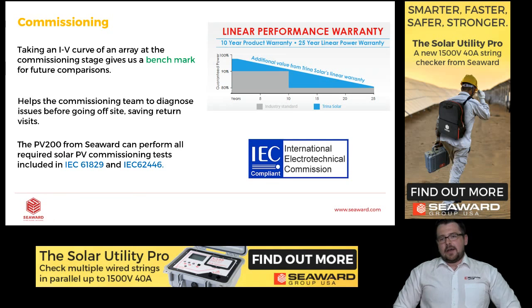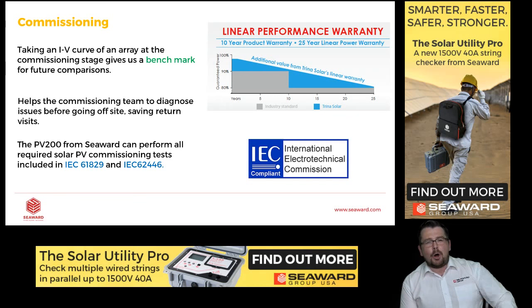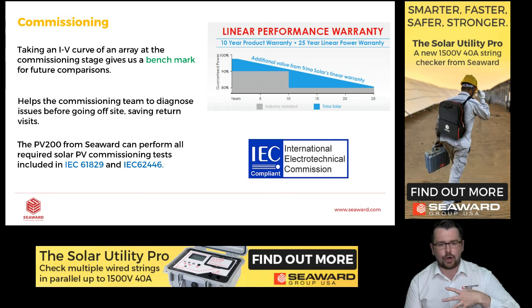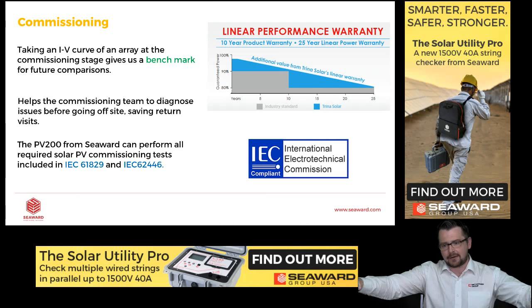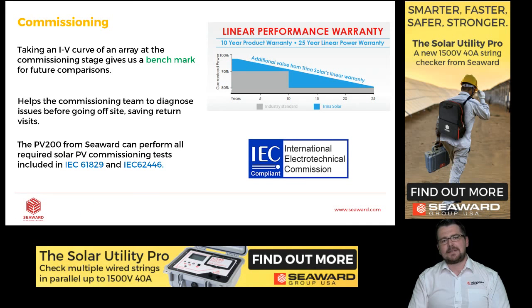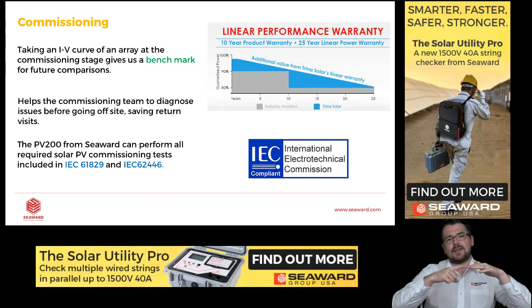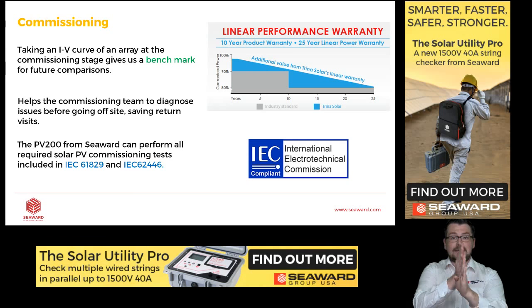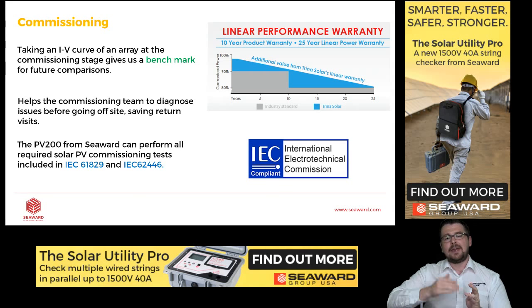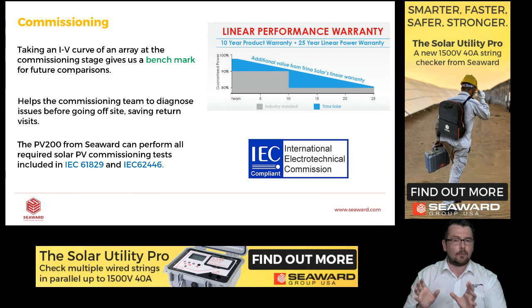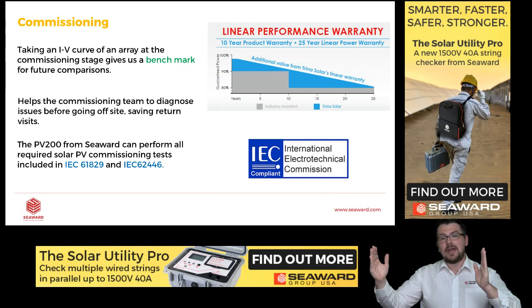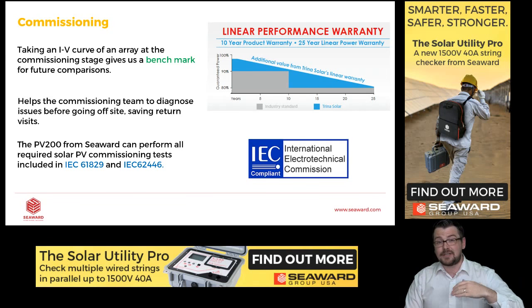A very good use for IV curve tracing, and probably the most popular out there in the PV world right now, is at the commissioning stage. To set the scene, the panels have come off the truck, all of the groundwork has been done, we've installed the panels, the combiner box has been fitted. So now we want to set a benchmark for all of our future tests. So we take a curve trace of that array and we set that, so that's year 0. And then when we come back to test the array in 2, 3, 4, 5 years time, or whatever the increment may be, we can compare our original IV curve to our current IV curve. And the difference between those two will give us the difference in the performance.